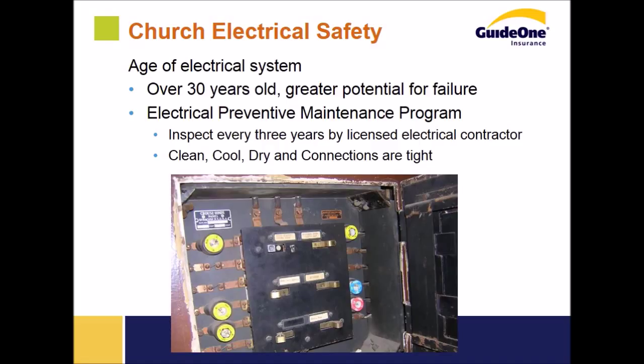We also recommend that every church have an electrical preventive maintenance program. It's very common for churches to have a preventive maintenance program for their heating, ventilating, and cooling system. It's much less common, unfortunately, for them to have the same type of contract for their electrical system. We'd like to see a preventive maintenance program in place where a licensed electrician inspects their electrical system every 3 years, checking for clean, cool, dry conditions and tight connections. A clean and tighten program can greatly extend the service life of an electrical system at our churches.